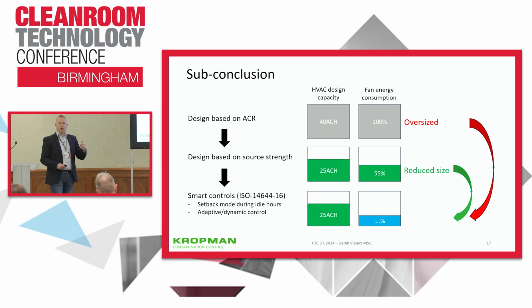So usually we apply a setback mode, meaning during idle hours when there is no occupation in the clean room, you reduce the air change rate even more. And another option is adaptive or dynamic control. And probably the next speaker is going to tell you more about that, I'm not sure. But the key message is that if you design on source strength, you will get a reduced size system, but also reduced size components.